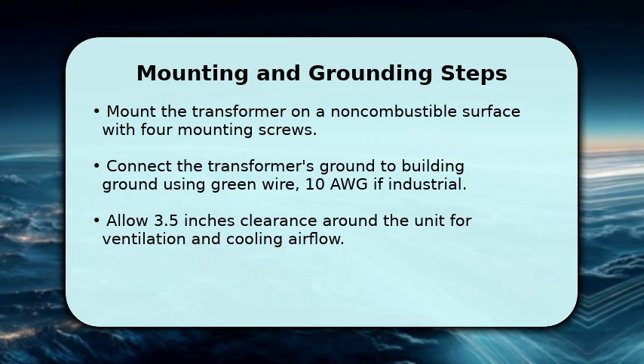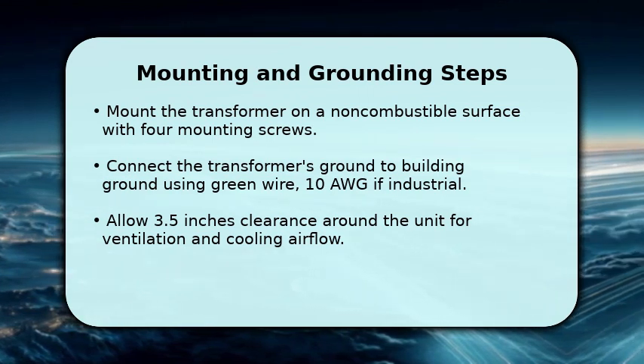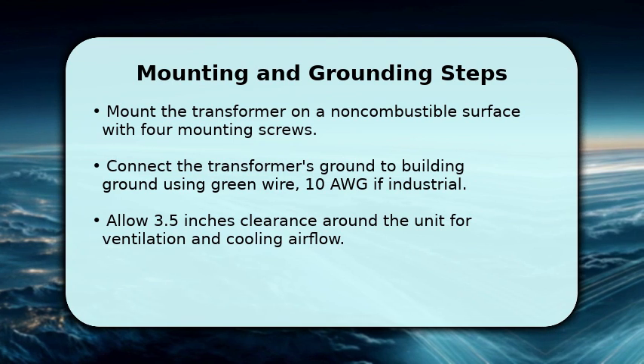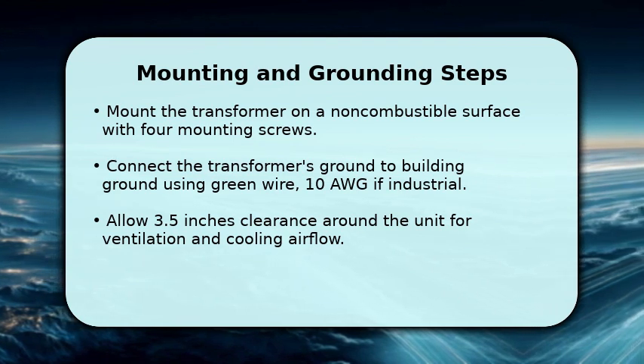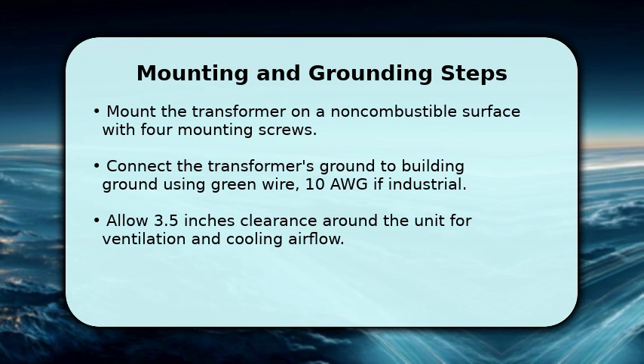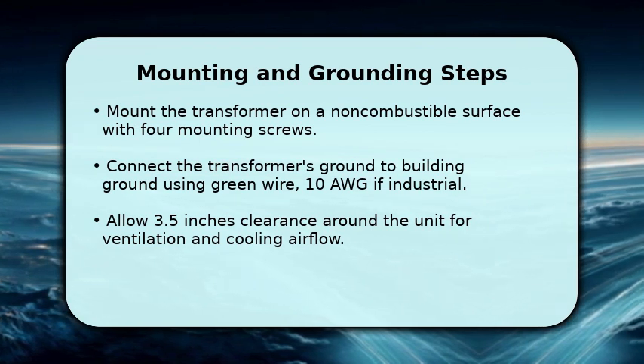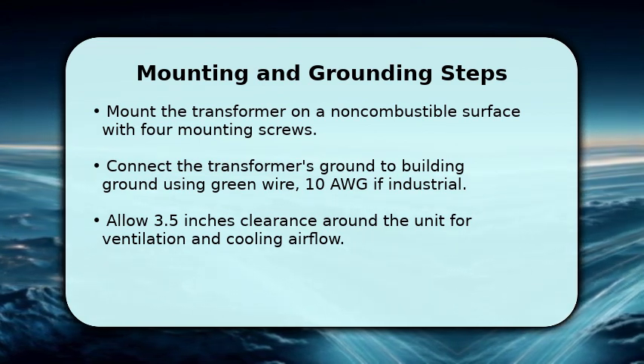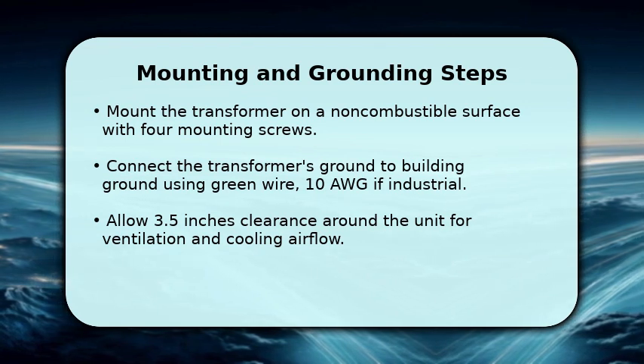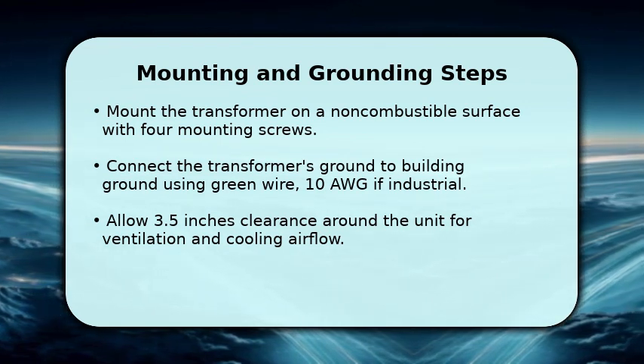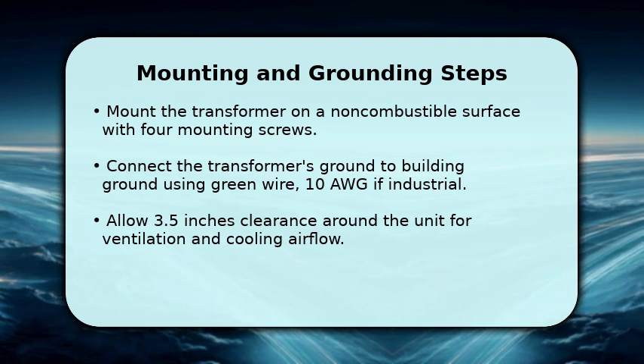Connect the transformer's green ground terminal to the building ground conductor. Use appropriate gauge ground wire. Use 10 AWG for industrial installations and 12 AWG for standard 20A circuits. Tighten grounding connections to specified torque values and confirm continuity with a meter before energizing the device.